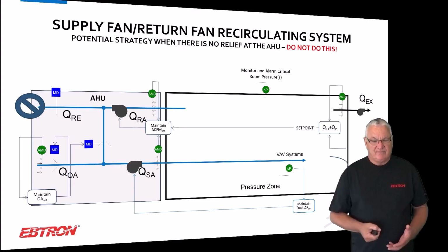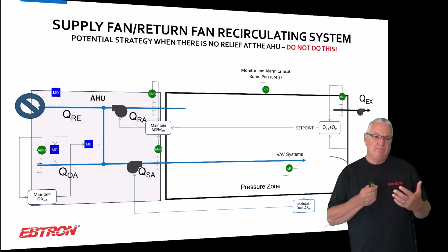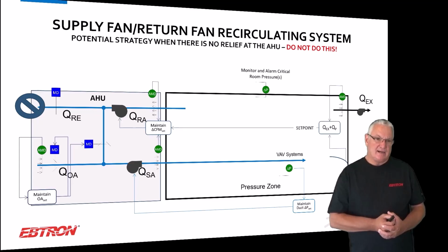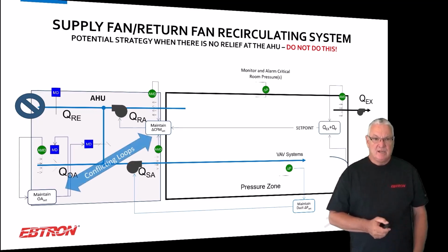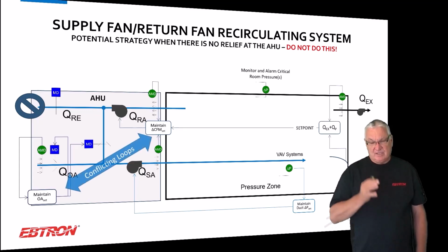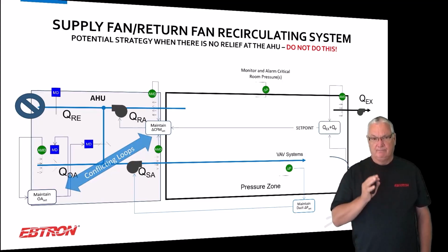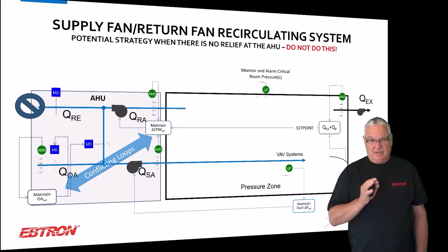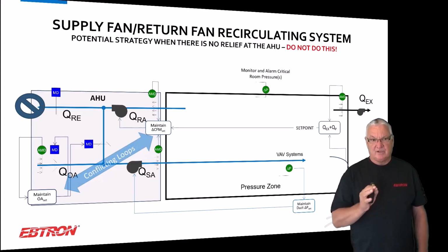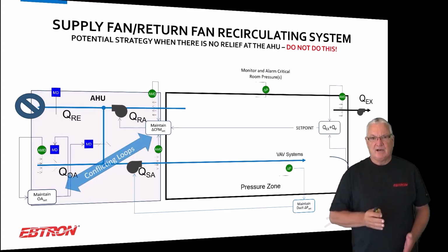You don't want to control that return fan on delta CFM in the outside air to the outside airflow station, because this is only when there's no relief at the air handler. These are conflicting, meaning that they're never going to equal each other. The supply minus return differential, because of instrumentation uncertainty, is never going to match the outside air. And so you're going to end up with a hunting problem. So you don't want to do that.